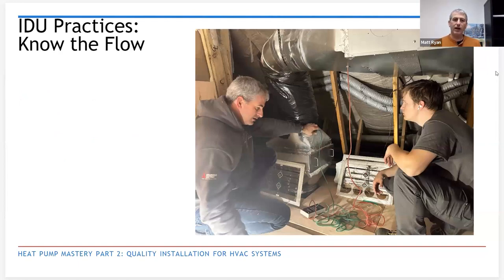Once you're all done, we like to go back and verify airflow. This was a new install with all new ductwork, so we were really able to control a lot of factors. On this particular one, we went back and verified airflow across the air handler, and actually did a room by room on this project. If you look really closely at this picture, yes, we are measuring two different points on the return air duct, just because we wanted to see what effect that 90 and short section of flex had. And it was pretty interesting. It actually jumped a fair amount just from that short distance. So that was a fun in-the-field experiment.